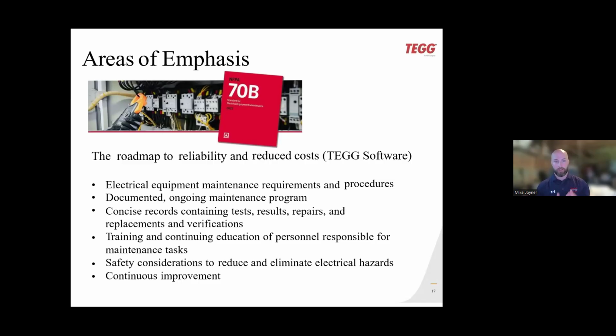We always did 3-year contracts. The first year would always be an EPM, an infrared scan, and any problems we'd find, we'd present to you guys. The second year would be a de-energized maintenance, no infrared scanning, and during that we'd take care of all the problems found in the first year, because that's the prime time to do it. Then the third year would be another infrared scan to ensure all the problems we fixed are still up to par and working properly.